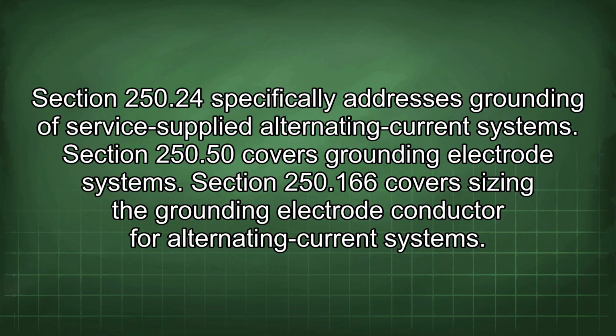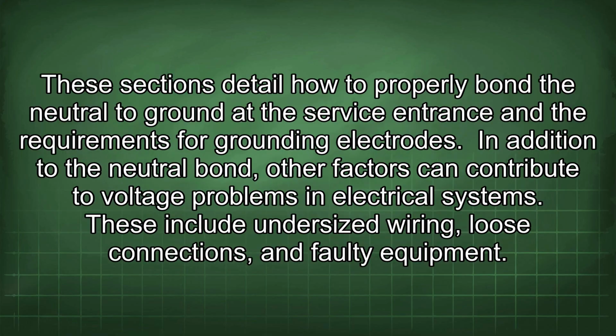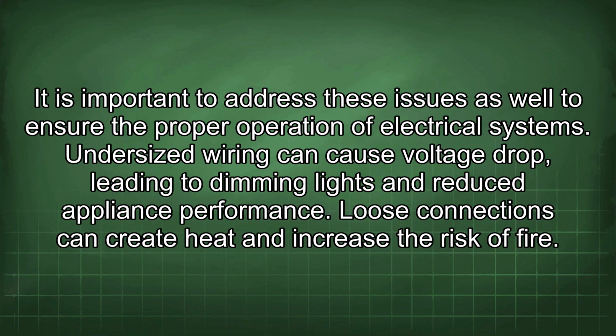Section 250.166 covers sizing the grounding electrode conductor for alternating current systems. These sections detail how to properly bond the neutral to ground at the service entrance and the requirements for grounding electrodes. In addition to the neutral bond, other factors can contribute to voltage problems in electrical systems. These include undersized wiring, loose connections, and faulty equipment. It is important to address these issues as well to ensure the proper operation of electrical systems.